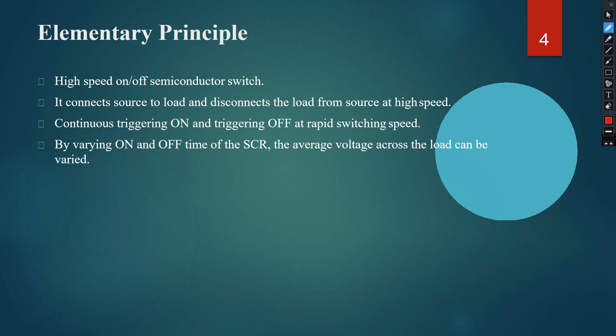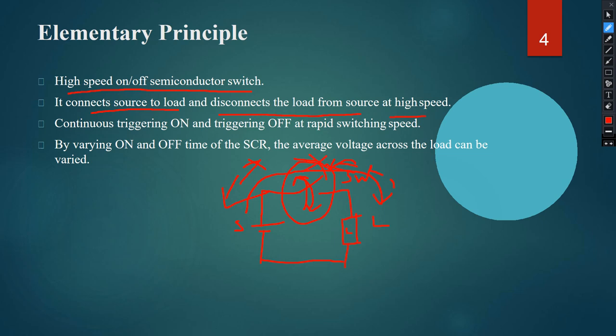The elementary principle of a chopper is that it is a high-speed semiconductor switch. It connects the source to the load and disconnects the load from the source at high speed. Whenever the switch is closed, power flows from the source to the load. When it is open, there is no flow of power. By continuously triggering on and off at rapid switching speed, and by varying the on-off time of the SCR, the average voltage across the load can be varied.